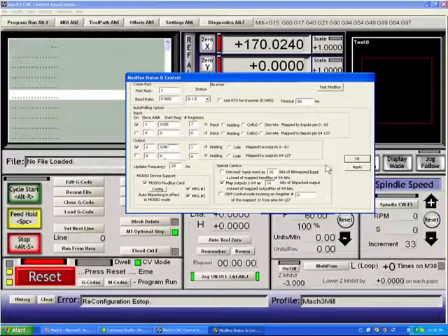Here under Special Control, we have some controls that allow you to configure a bit differently. Normally, each 16-bit word sent to a ModBus control is a 1 or a 0 representing the pin number of the position of the register. In this case, however, you can check a box which says use each input word as 16 bits of bit-mapped input. Instead of sending 64 16-bit words, you could send one 16-bit word and have each of the bits within that word correspond to pins 0 to 16 in your device, in your ports and pins configuration for various input signals and output signals.